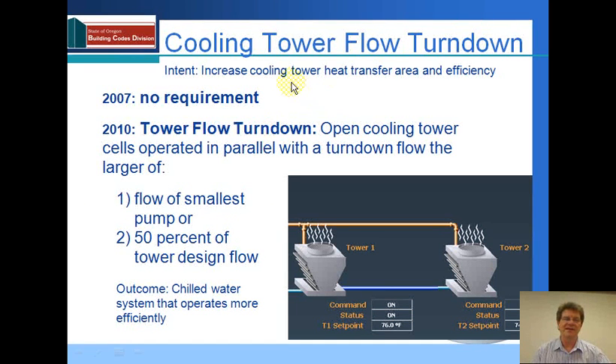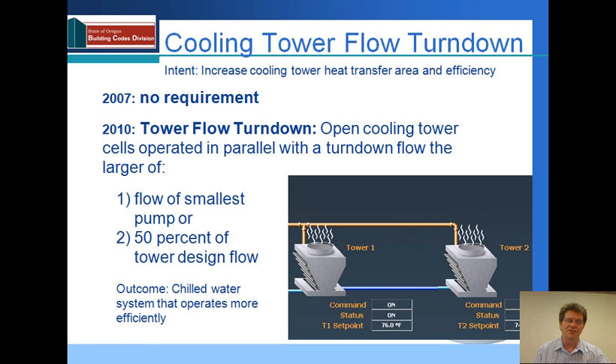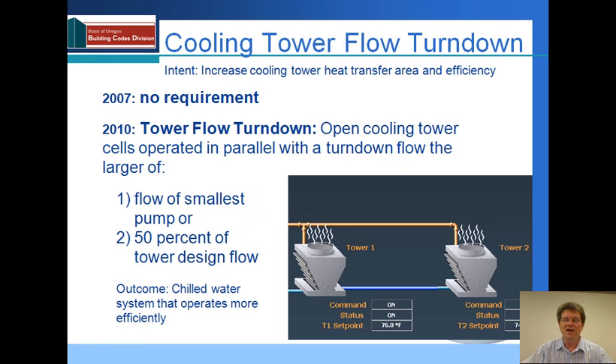Cooling tower flow turndown: this doesn't apply when you've got a single tower with a single cell. But if you've got multiple towers or a single tower with multiple cells — meaning multiple fans — there's a requirement that instead of just shutting one tower off, multiple towers run at part load. The towers need to be operated in parallel with turndown flow to the largest of the smallest pump or 50% of the total tower design flow. This saves fan energy use on the tower, and some care must be taken in tower selection.